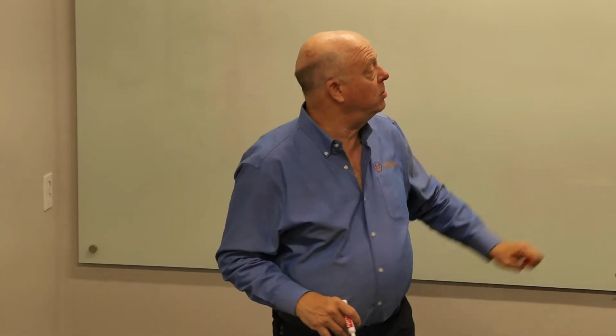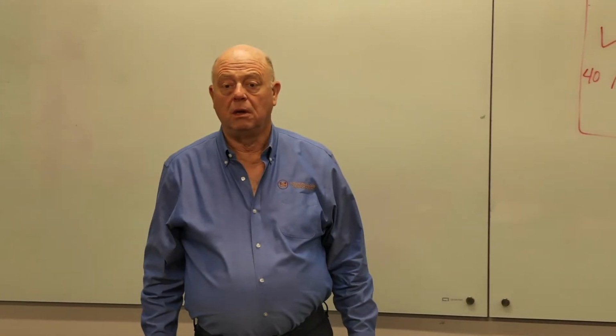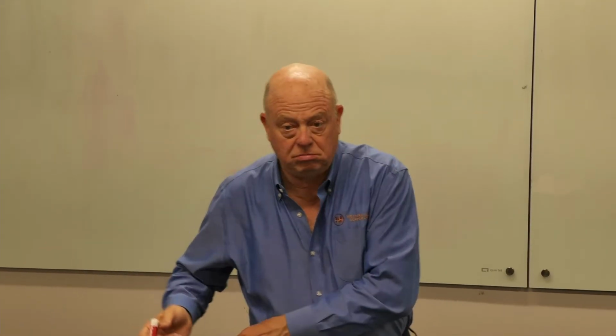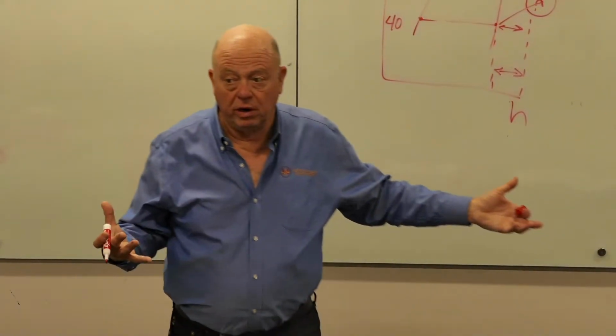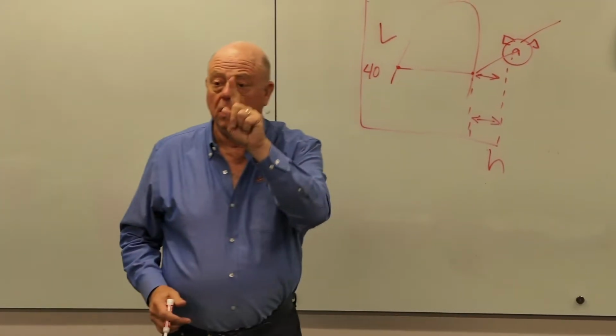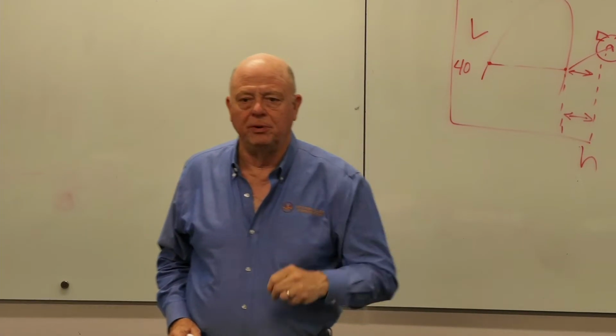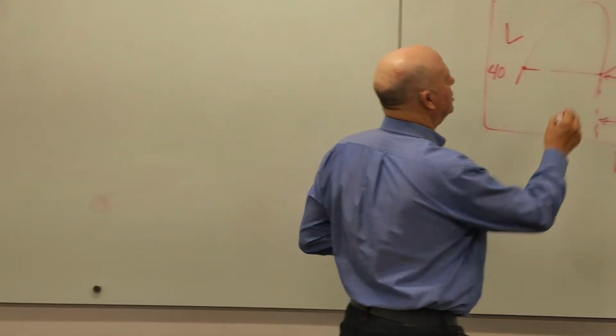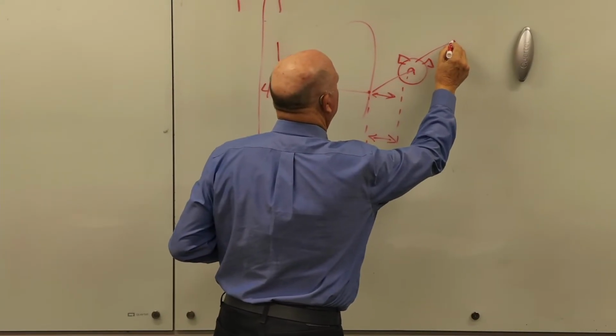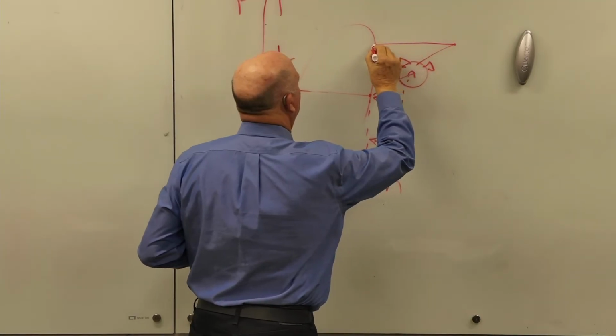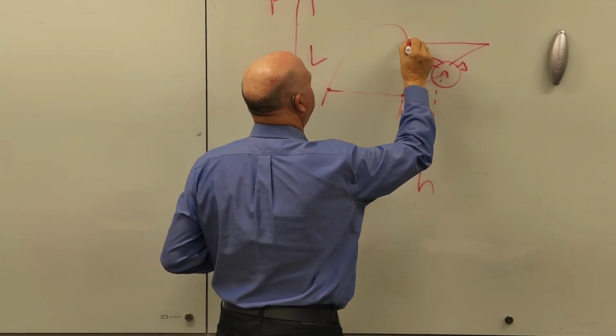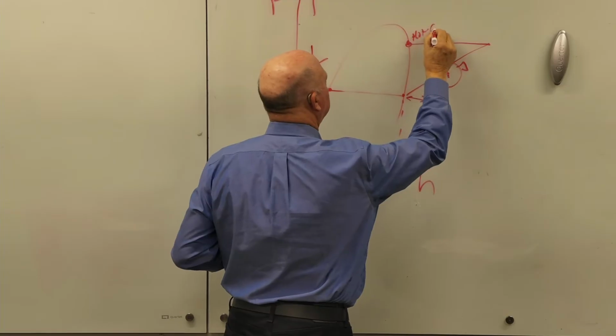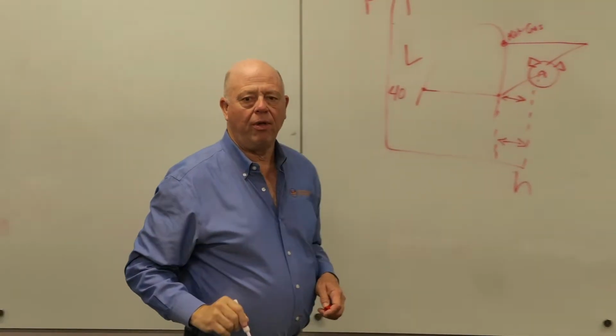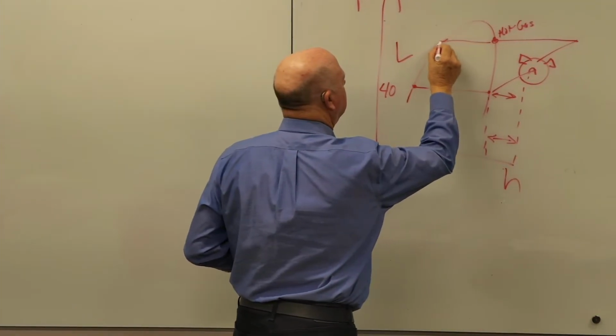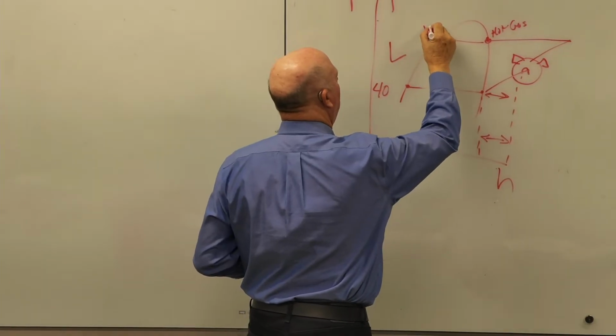In other trades, not HVAC, some people call compressors a pump because you could say it's pumping the refrigerant, right? It's moving it. So that's one goal. The other is it raises the temperature and pressure. So it gets it up to some temperature and pressure, and then we route it over to a condenser. And at this point, it's all hot gas. And then it goes through the condenser, and at this point, it's now all hot liquid.